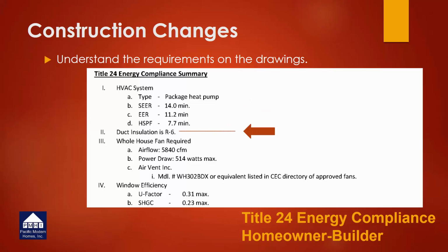Same thing goes for duct insulation. Duct insulation is regulated. Most commonly, it's R6. Sometimes it needs to be R8, which is more expensive, so you need to know which one it is. In addition to the duct insulation, if you're installing a whole house fan, which is very common in the Central Valley or in the high desert areas, we'll help you identify what the airflow and the power draw should be for that, and we'll even give you a model number that you can use for bidding purposes. Does not mean that you must install this specific fan. Just means that you must install a fan that has that general airflow and power requirement. You can always pick something else out of the CEC's directory of approved fans, just based on your bids. But this is the baseline of where you need to be.